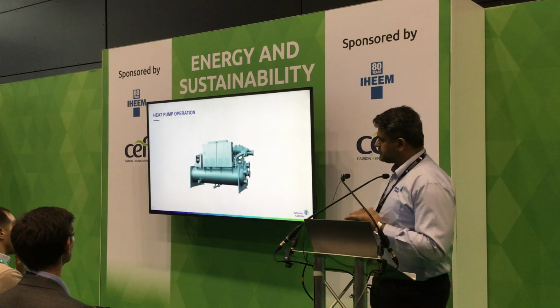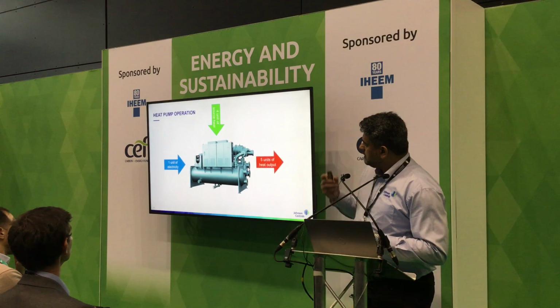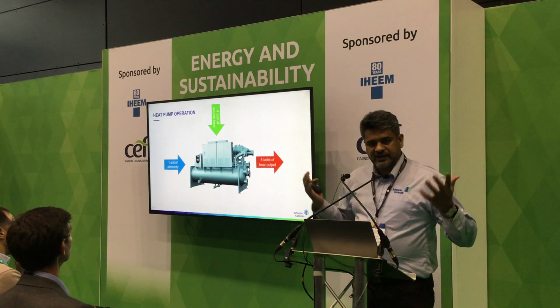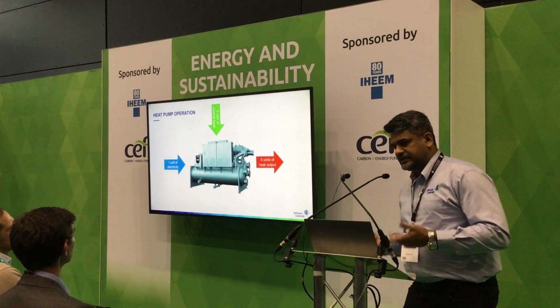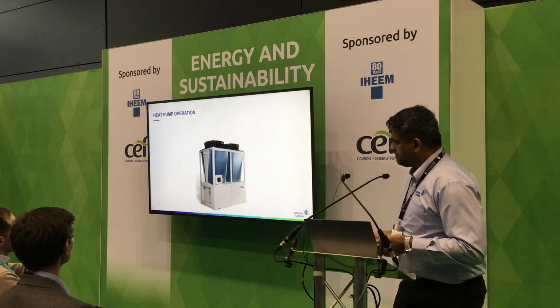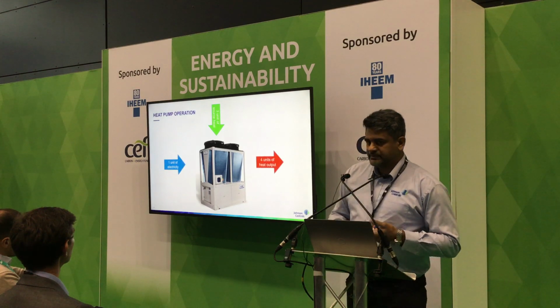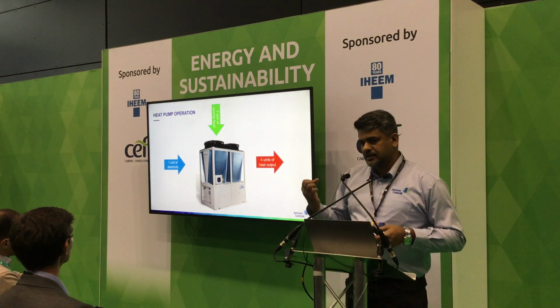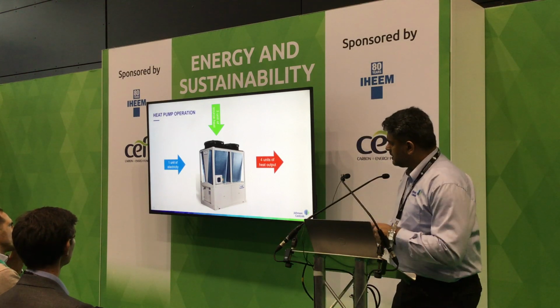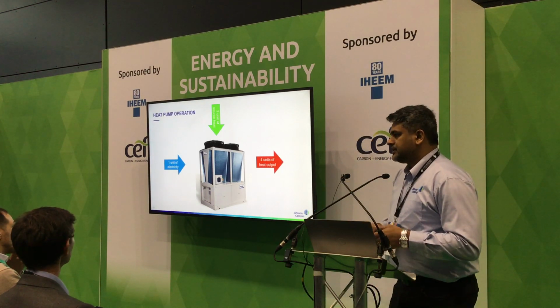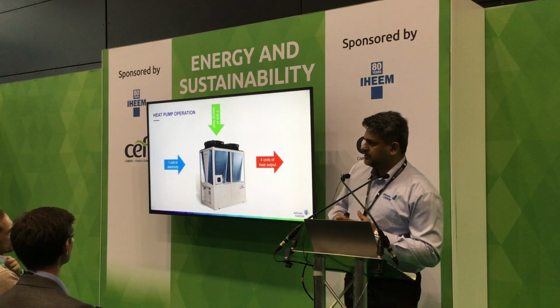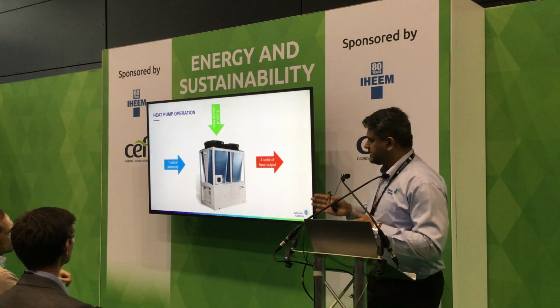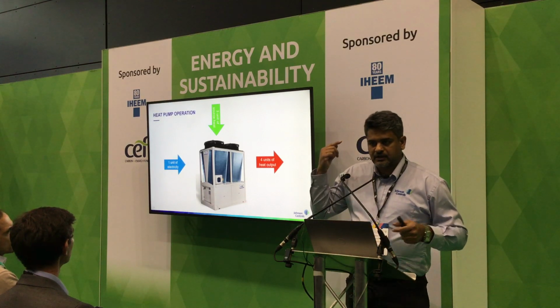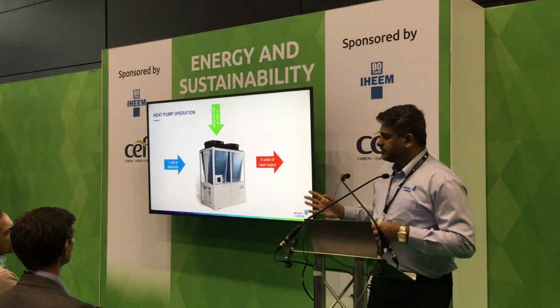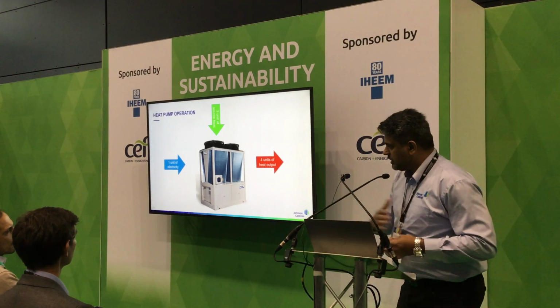How does it operate? If you power up a water source heat pump with a unit of electricity, it takes about 4 to 5 units of heat from the source and delivers 5 units of heating output. For the air source heat pump, with that same electricity, because the medium it takes the energy from is a lot less efficient, you get about 4 units of heat output. And this is your seasonal figure across the board. Typically these units are designed for a single point, worst case scenario, but 4 units of heat output is across the board on a year-round operation.